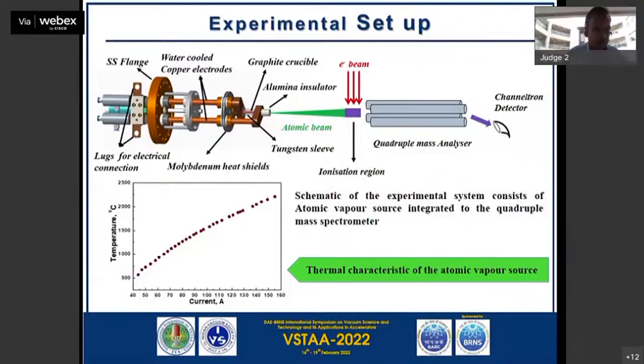The thermal characteristic of the atomic vapor source I have shown here. That source can go up to 2200 degrees Celsius. Actually, I am using a pyrometer with range 550 to 2500 degrees Celsius. Yes, I cannot measure below 500 degrees Celsius. So my data I have shown in current.